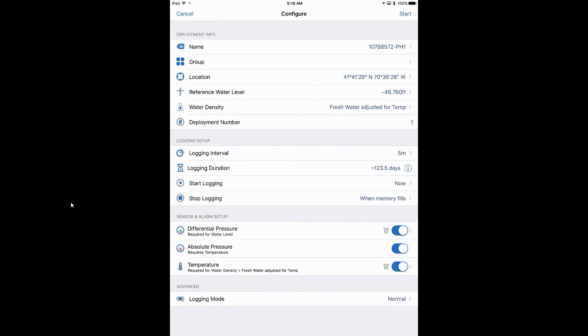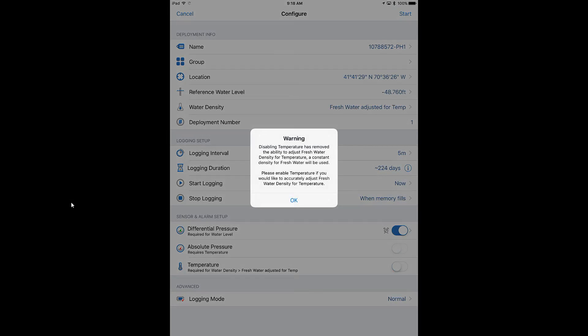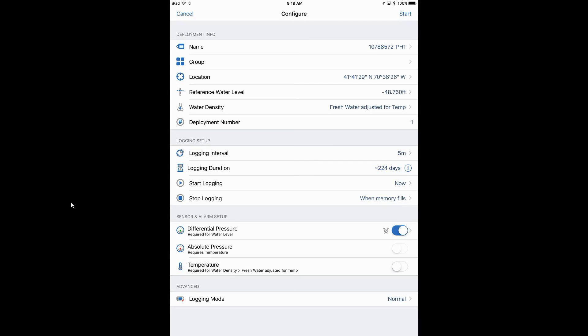Below that is where we can enable sensors to log. We want to get differential pressure, which is the difference between the barometric and the in-situ measurement. Typically you'd want to leave all of these on — if you turn temperature off, it warns you that you won't be able to use the fresh water density compensation, so it turns off that measurement too since it's not valid. I'd suggest leaving them all on for your application.